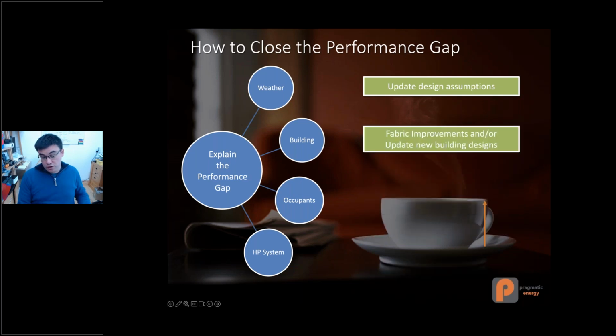It could be that the performance gap has got nothing to do with the heat pump itself or the weather - it's the building. Maybe the building hasn't performed as well as we think. In an extreme case, we might retarget some fabric improvements, or look at the next stage of a project and update the building designs where things didn't work well. But if you've got all the data flowing out of a heat pump, you can understand what the demand was - not the electrical use, or how warm someone left the house, but the actual heat loss of the building, how performant it was, whether it was built and designed the right way.